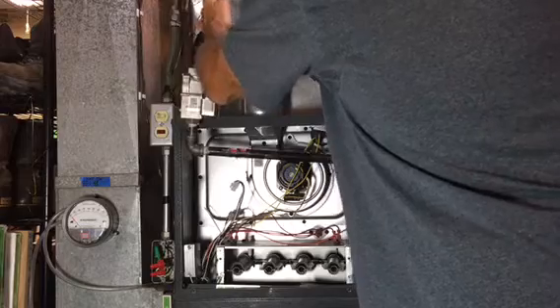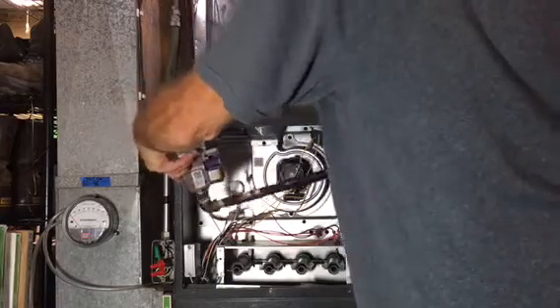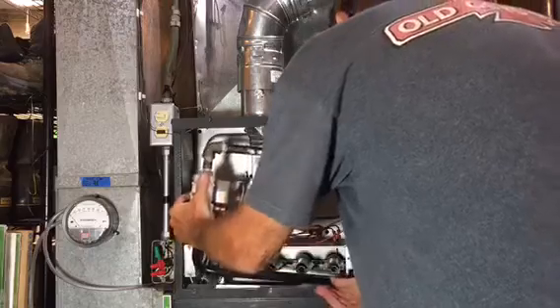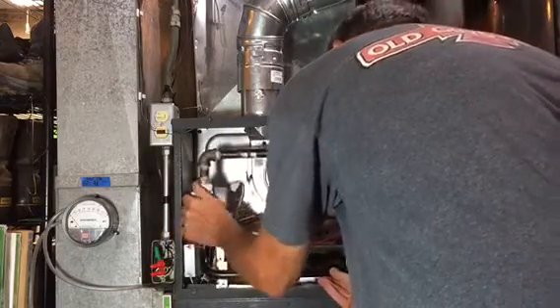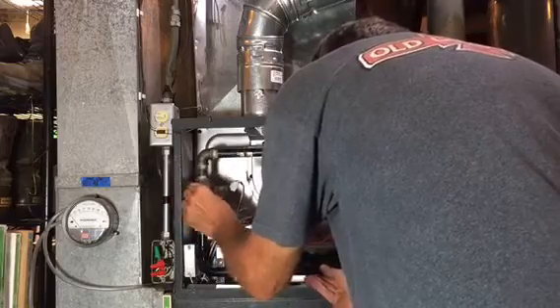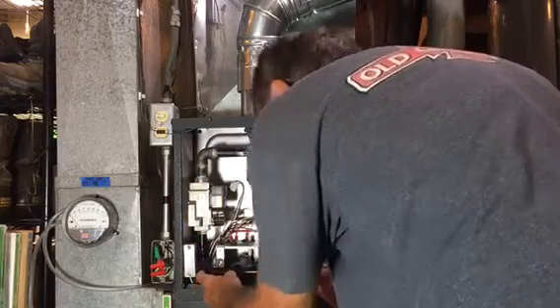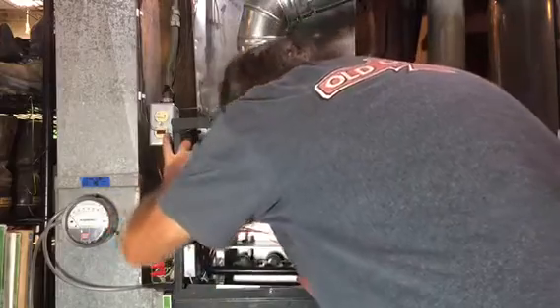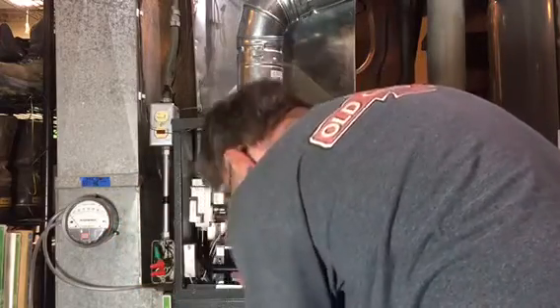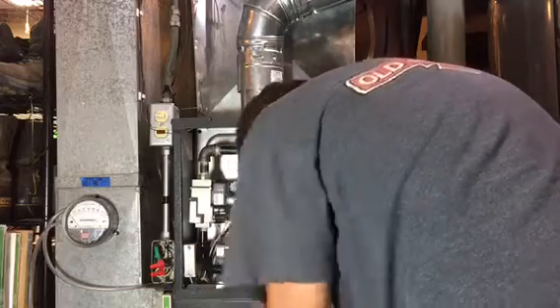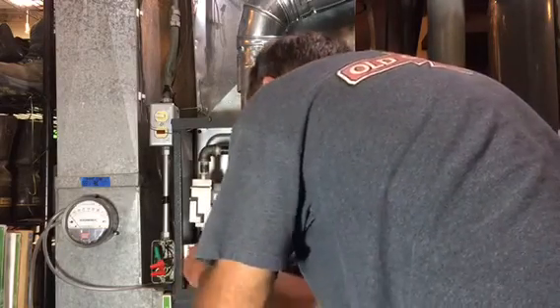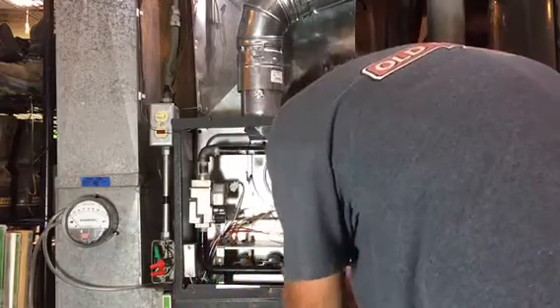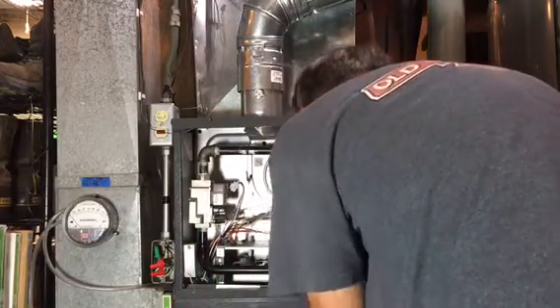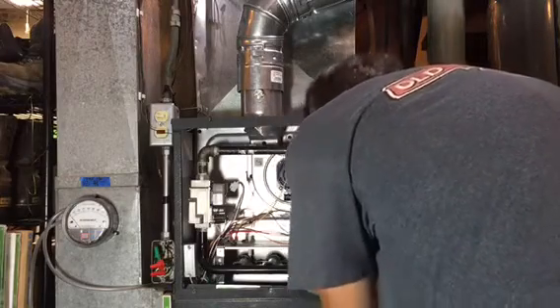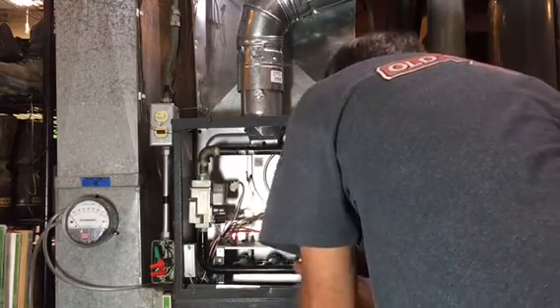Now we're just going to lower the manifold from its storage position. Conveniently rotates around, and this will position the burners. It only can really go in one way, so as long as you get the 4 sheet metal screws again, in properly, we'll have our gas distribution InShot burners in.